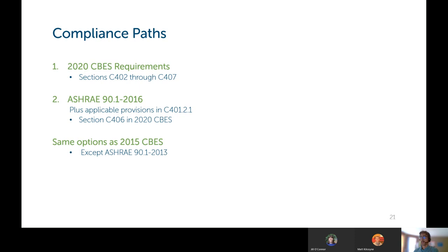90.1-2016 plus applicable provisions in section C401.2.1 and also section C406, which is some additions that need to be put on top of ASHRAE 90.1-2016. And these are the same options as in the current 2015 energy code, except that was using the previous version of ASHRAE 90.1-2013. So that has been updated to ASHRAE 90.1-2016 for the 2020 code.